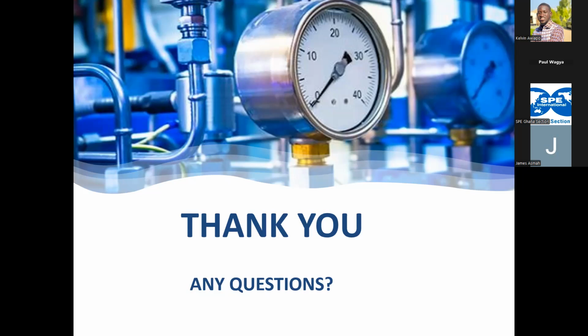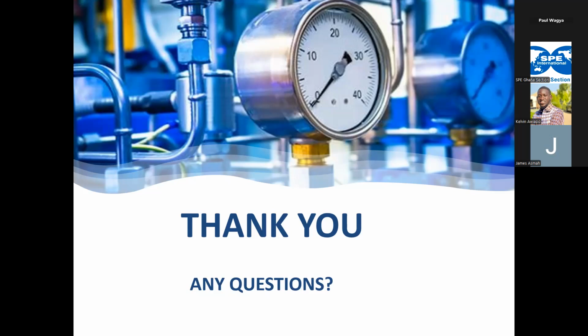If I get you clearly, I mean the current base transmitters or instrumentation that we have, and now the new smart ones, those can do some diagnosis on themselves to show you a fault based on the readings and the recordings. So it can tell you that this transmitter is developing some fault, and then you need to change it or you need to work on it. I don't know if it clarifies, or maybe you can clarify the question.